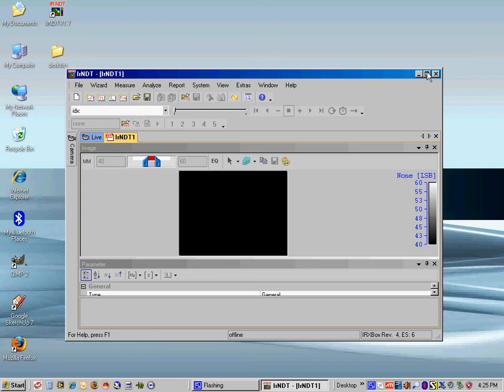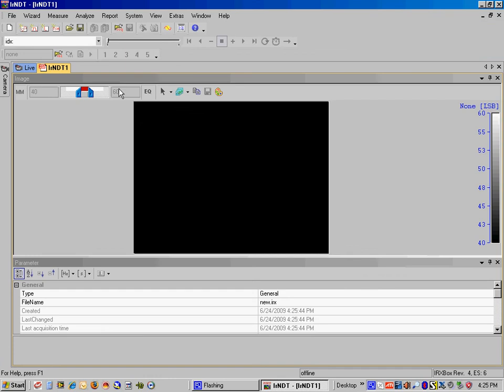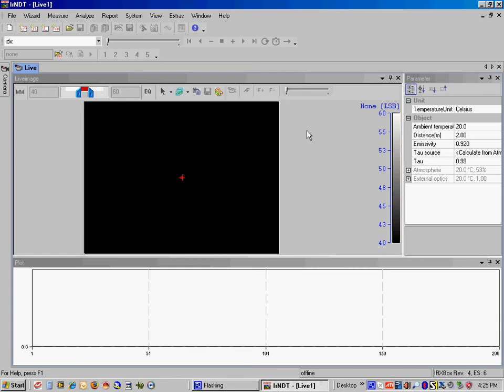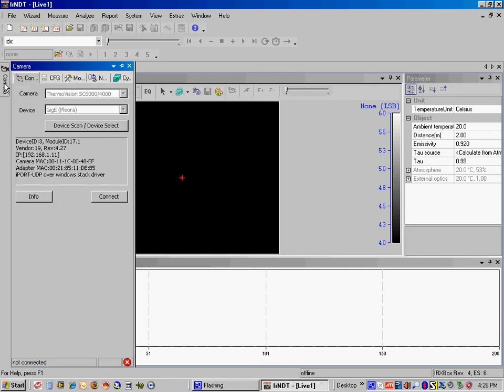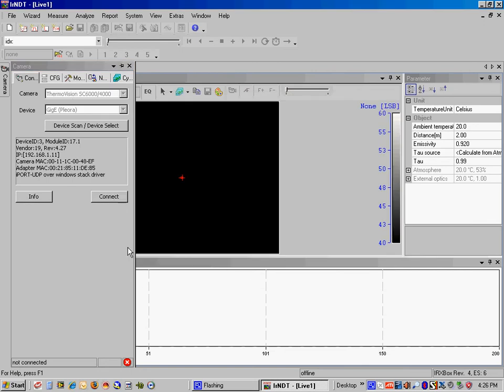The software, when it first opens up, has this default setting with the default workspace. We're going to go ahead and clear that because we're going to create our own for lock-in thermography. First, we need to also make sure that we're connected to our camera. So I'm going to go ahead and do a quick device scan, make sure it's in the system. It's there, and connect to it.